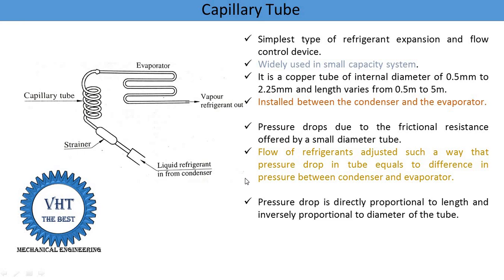If we require a higher pressure drop, we select a smaller diameter tube. There are a number of possibilities — suppose the required pressure difference from condenser to evaporator is 6 bar. For that 6 bar pressure difference, a number of diameter and length combinations are possible. If we select 1 mm diameter, the length is different; if we select 0.5 mm diameter, the length is different. Once we select a particular diameter and length for a certain pressure drop, it is fixed for that particular system.